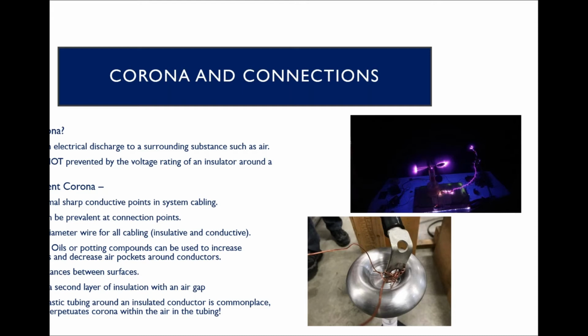One of the misconceptions is that if you cover your conductive cabling in a second layer of something like plastic tubing, then it will cut that down. The misconception is that that will completely get rid of your corona, but really what happens is now you're just generating the corona within that tube, and it just kind of increases the air density within that space, causing more corona to generate. So if you're going to be doing tubing around all of your conductive cabling, it really should be filled with a substance that's not air. It should be filled with an inert gas or some kind of insulative oil.